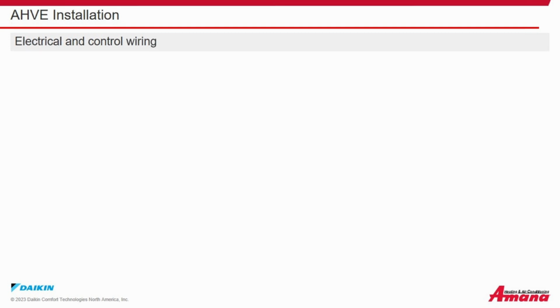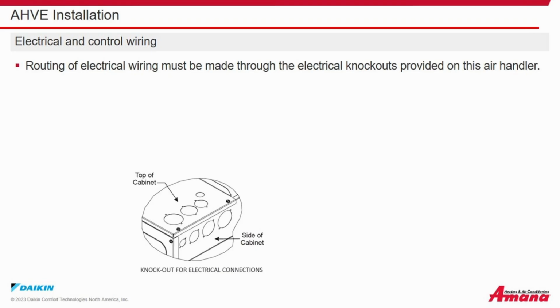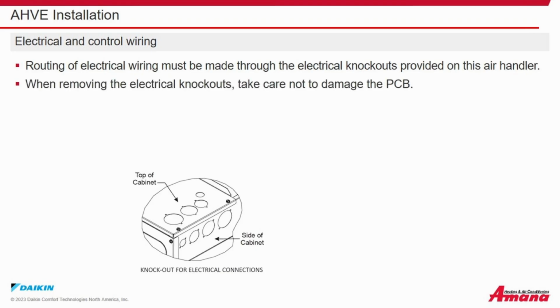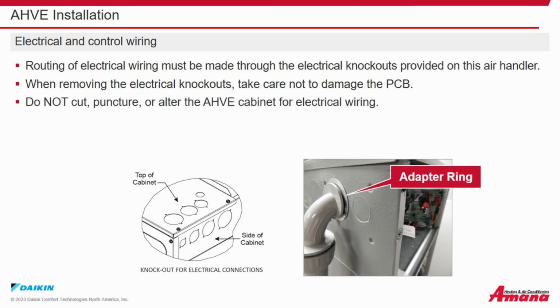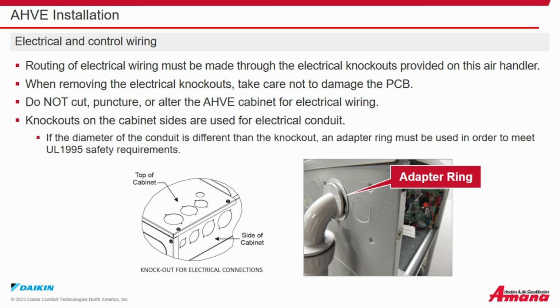Electrical and control wiring. Routing of the electrical wiring must be made through the electrical knockouts provided on this air handler. When removing the electrical knockouts, be careful not to damage the printed circuit board. Do not cut, puncture, or alter the AHV cabinet for electrical wiring. Knockouts on the cabinet sides are used for the electrical conduit. If the diameter of the conduit is different than the knockout, an adapter ring must be used to meet UL 1995 safety requirements.